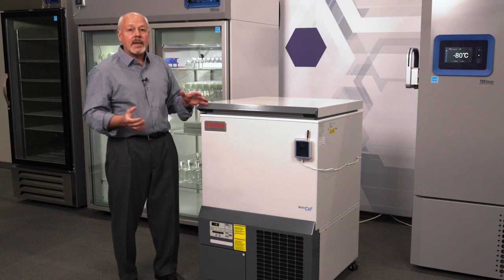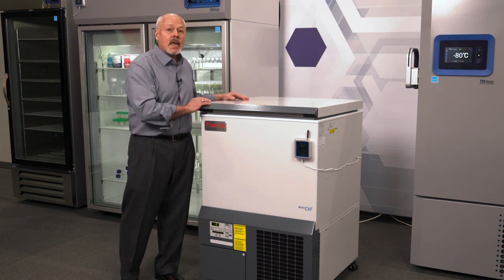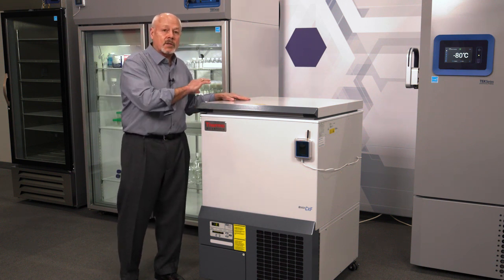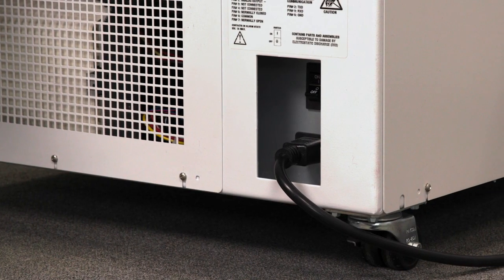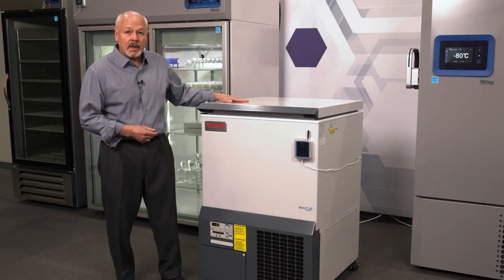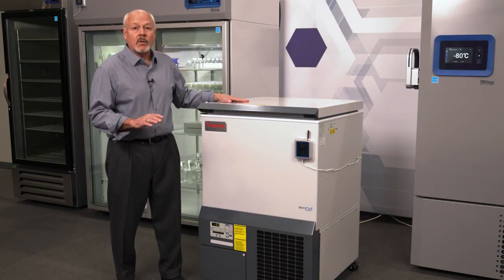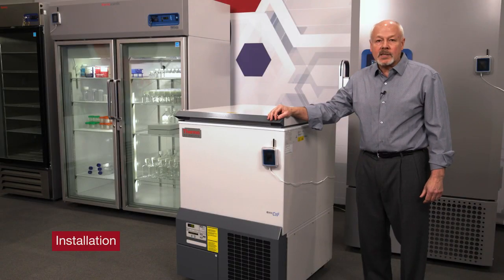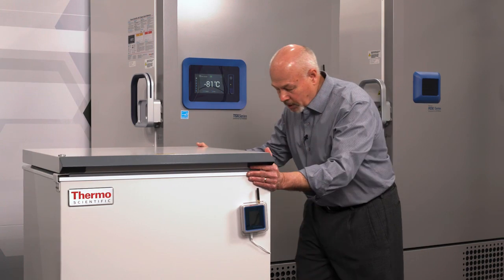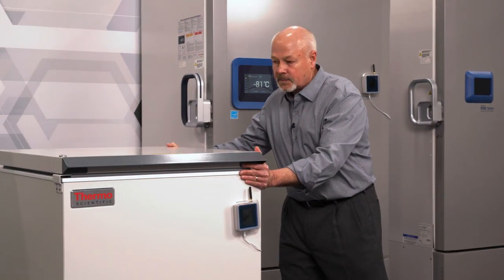That R value means that should power be lost, it will take 3.5 hours for the unit to warm between -80 and -50 C. This unit operates on 115 volt standard electrical power with a 15 amp circuit. It uses very little energy, only 4.3 kilowatt hour per day. Installation of this unit is actually quite simple. It easily rolls into place on the 4 mobile casters.